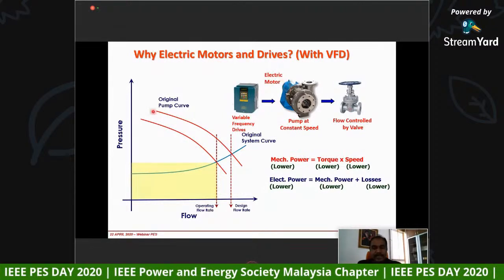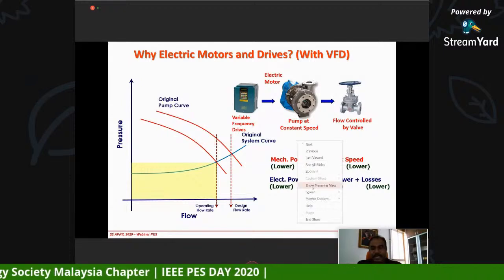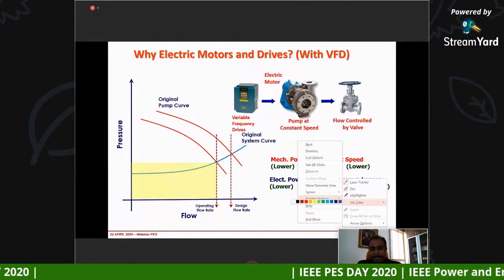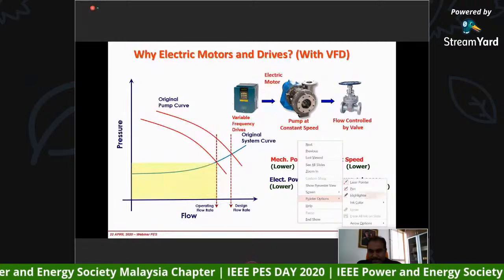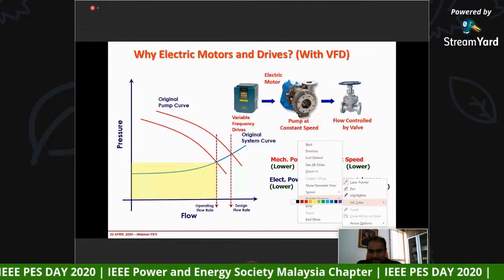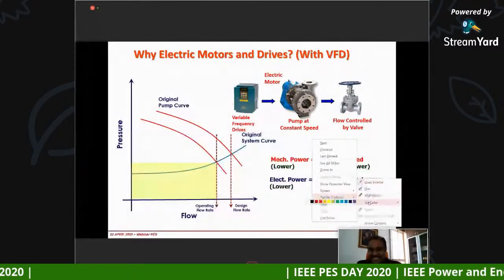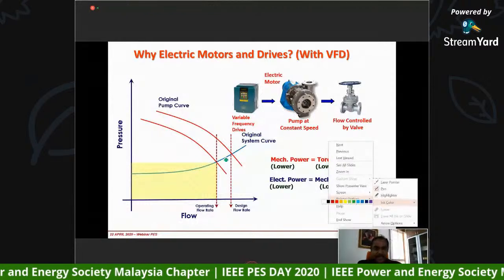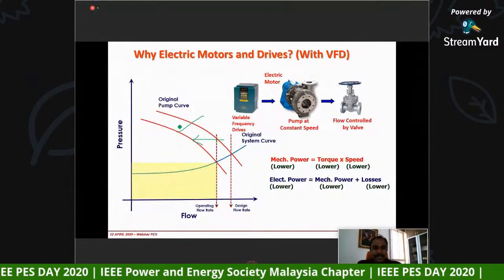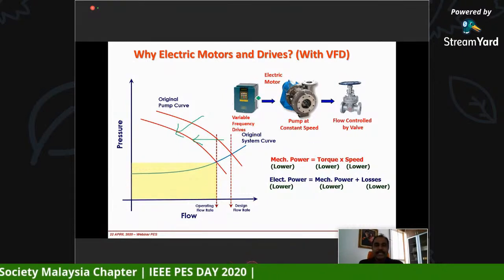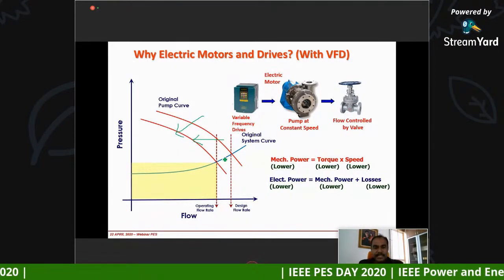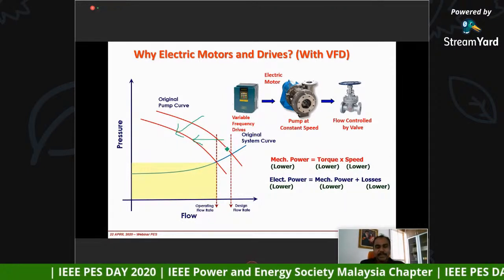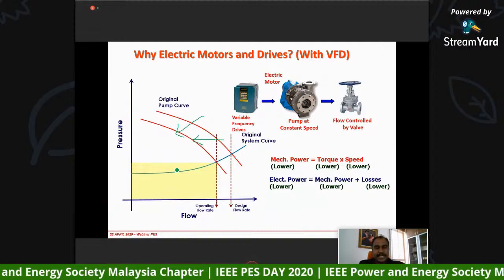When I do that, basically what happens is the pump curve will be shifted. As you can see here, the pump curve will be shifted. Okay. Maybe a different color. Sorry. So if you notice, the pump curve will be shifted. Okay. The pump curve is actually shifted. Why is it shifted? Because we control the pump speed. Okay. Because this particular curve is only true for that particular speed. So once you change the speed, of course, the pump curve will be moved. And therefore, what you see here is that your operating point now is here.